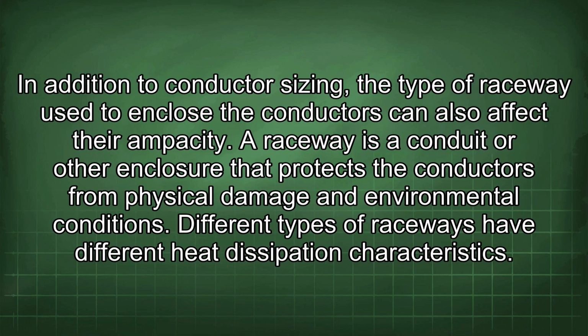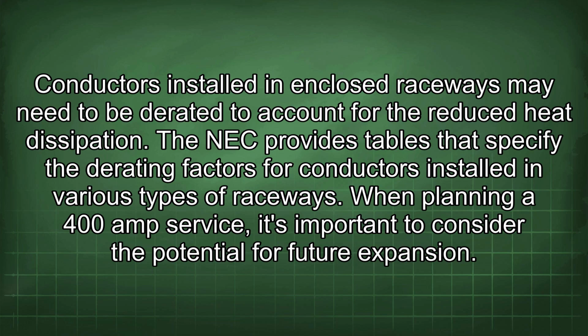In addition to conductor sizing, the type of raceway used to enclose the conductors can also affect their ampacity. A raceway is a conduit or other enclosure that protects the conductors from physical damage and environmental conditions. Different types of raceways have different heat dissipation characteristics. Conductors installed in enclosed raceways may need to be derated to account for the reduced heat dissipation. The NEC provides tables that specify the derating factors for conductors installed in various types of raceways.